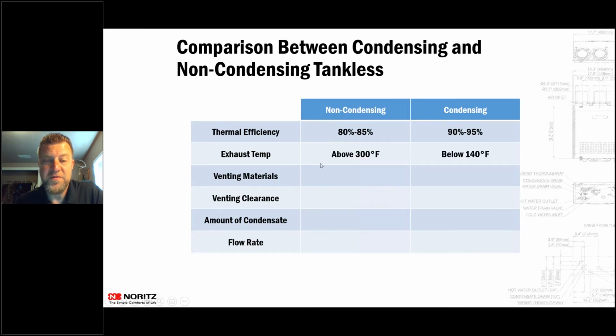Exhaust temperatures with the non-condensing could be 300, 400 degrees coming out. With condensing, the maximum temperature you'll see coming out of a condensing unit is 140 degrees. We have to keep that temperature below 149 to be able to vent in PVC. We do have some commercial units though that you can turn up to like 185 degrees, where that stack temperature could get up to 159, 160. Same thing with our combination boilers. If you are going to that higher temperature, they suggest that you vent in CPVC or polypropylene if you're going up to 180 degrees.